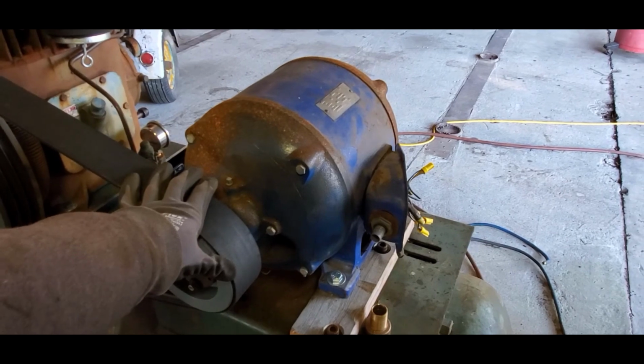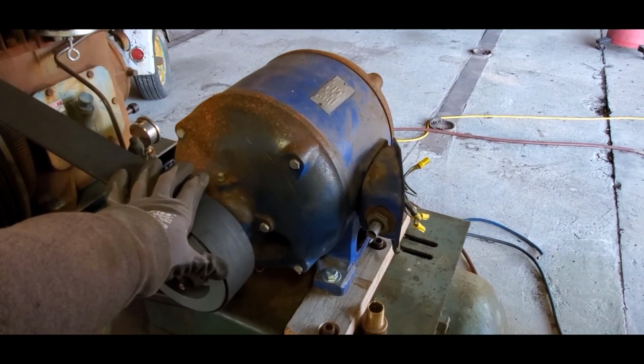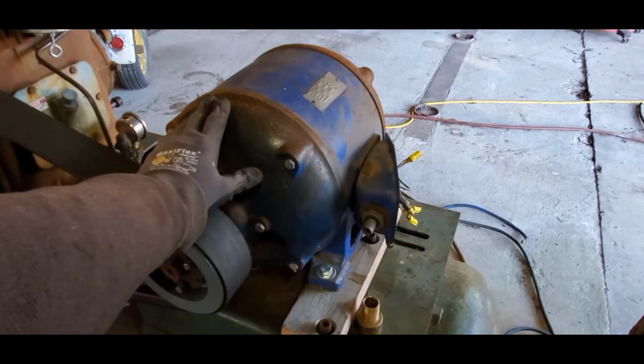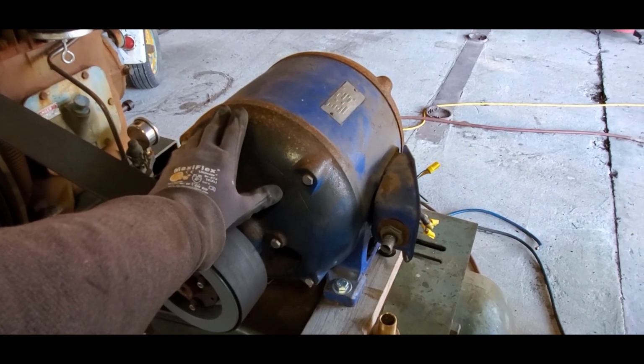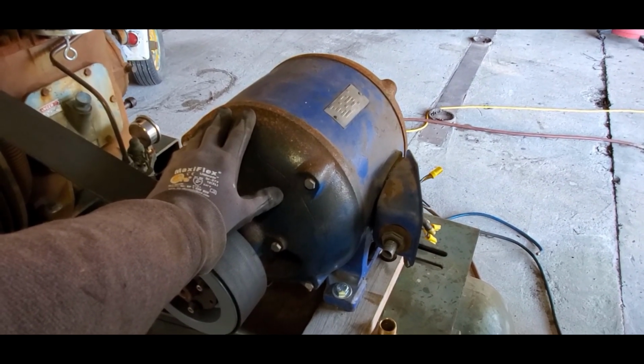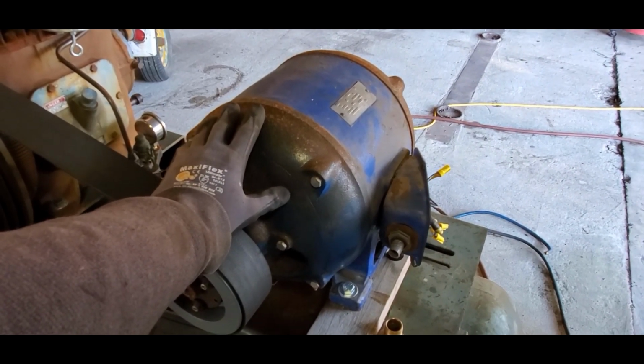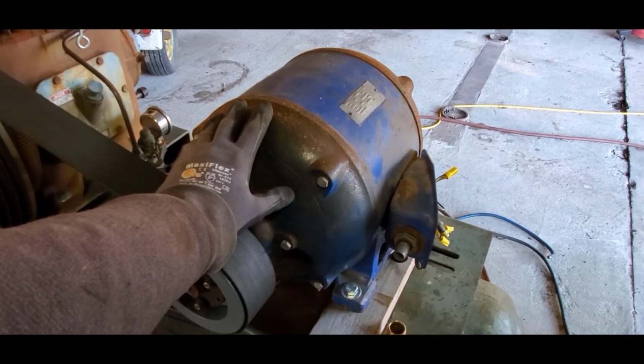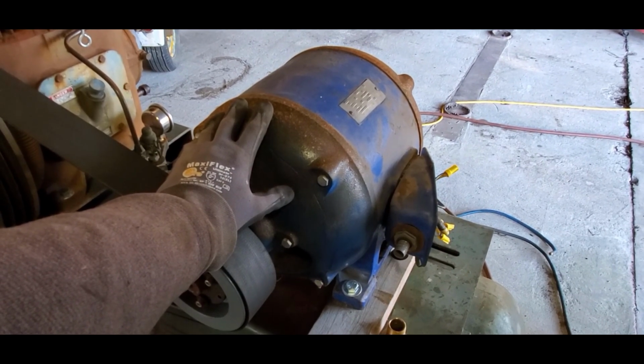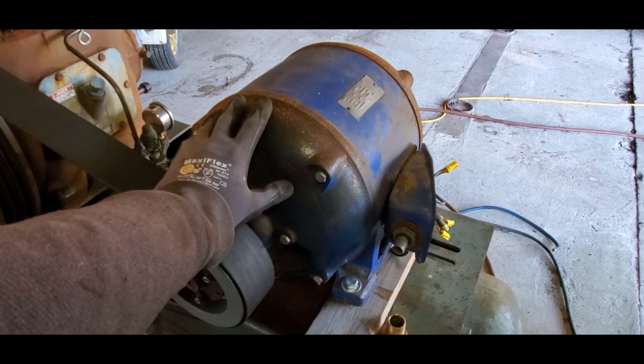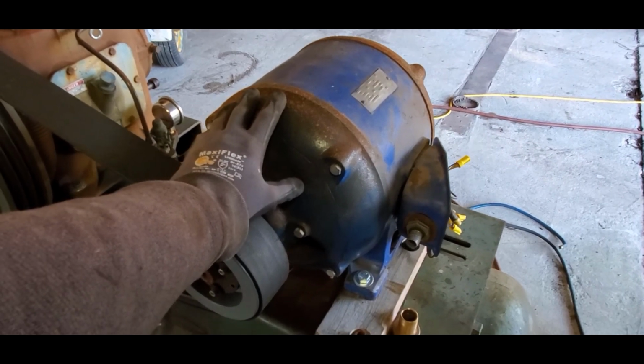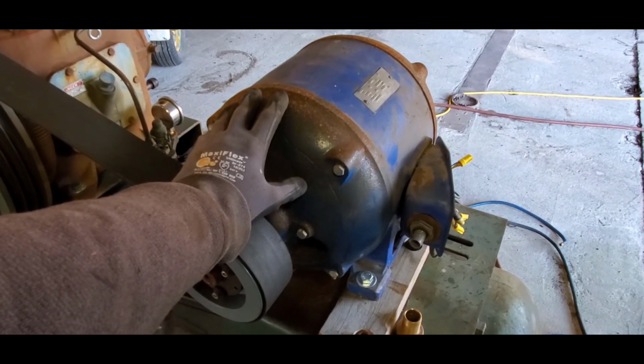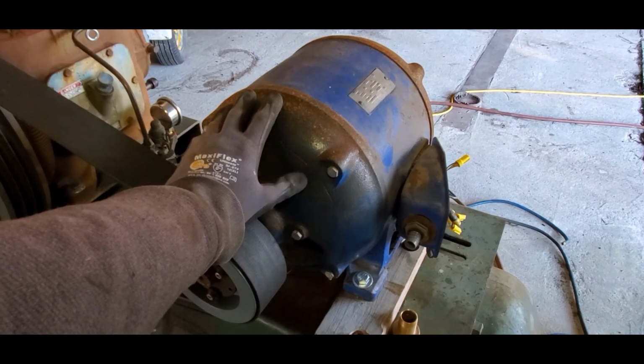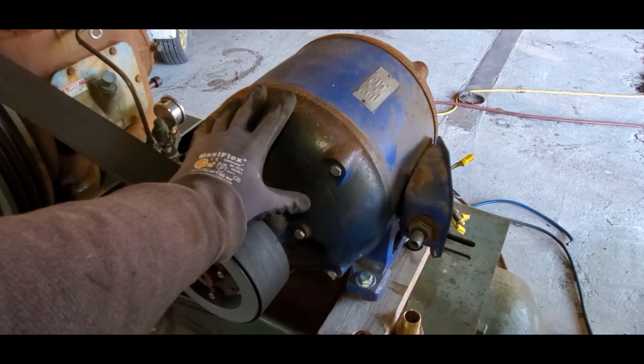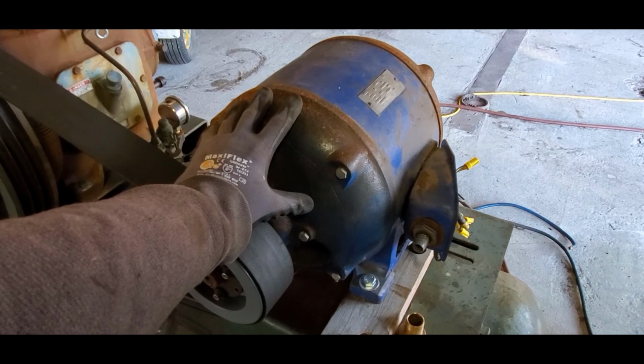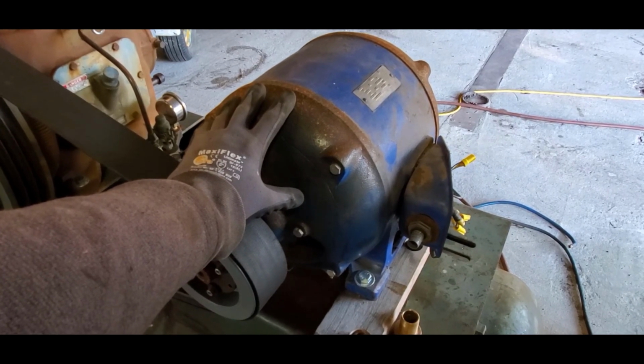And if I do that, I can leave the 3-phase motor on the compressor, and if I put a pressure switch on or a couple of pressure switches, I can do some really neat things. When the tank would get up to pressure, a switch could send a signal to cut the speed of the motor by 40–50% and let things slow down, and a second pressure switch could shut it off, but it could keep the tank topped off when I'm doing a job that requires a lot of air.